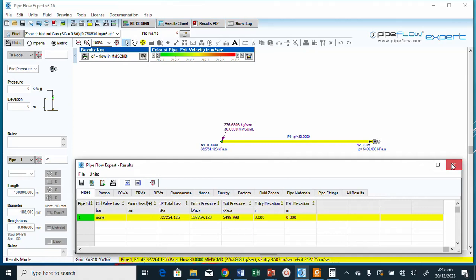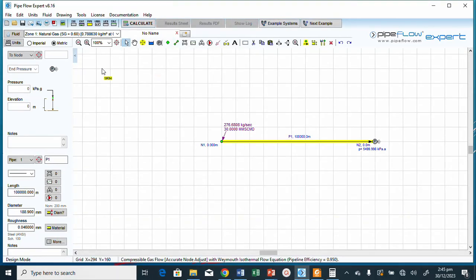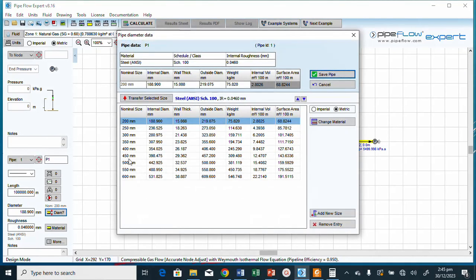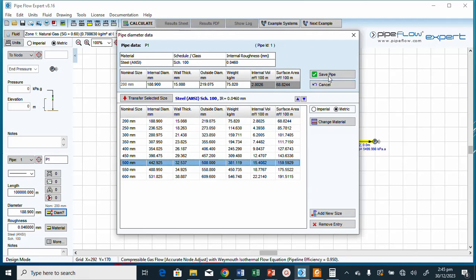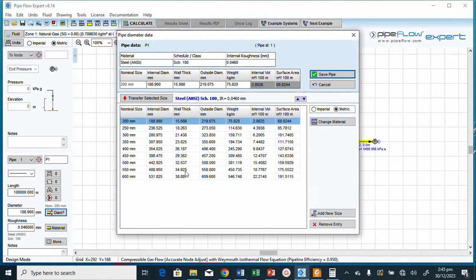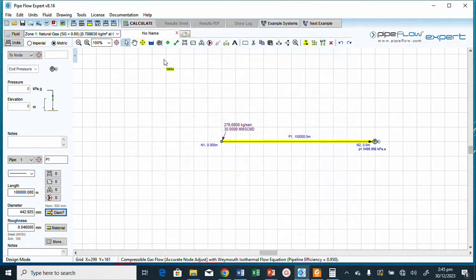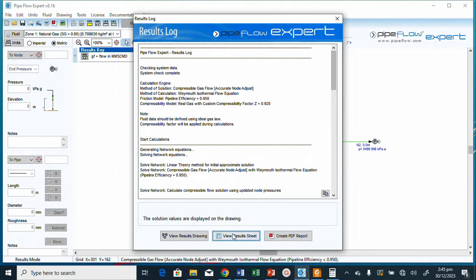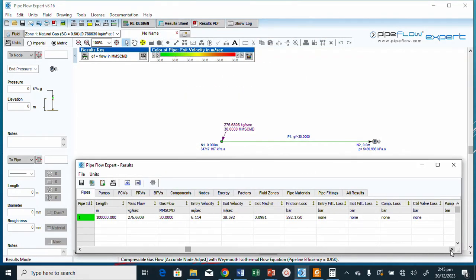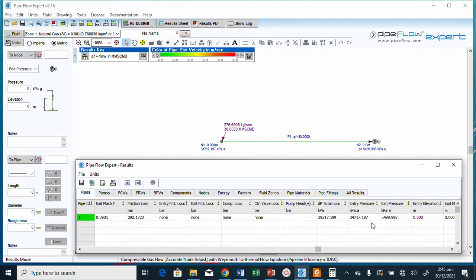We go back to the software and increase the pipe size. Let's select 500 mm — transfer the selected size, click Save, then Calculate. The inlet pressure drops to 34,000 kPa, a drastic reduction. We need to decrease it further.